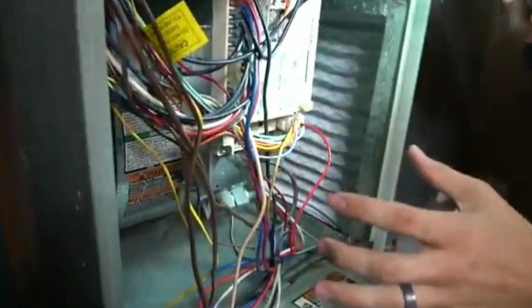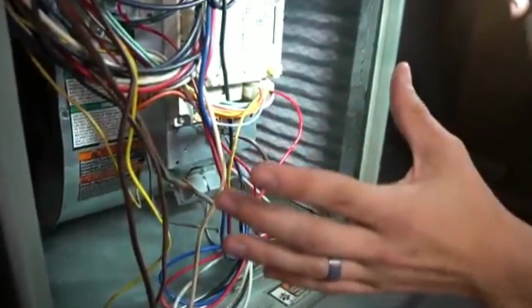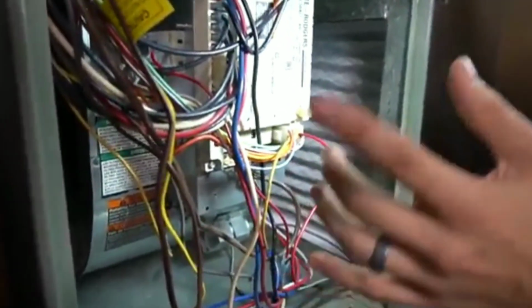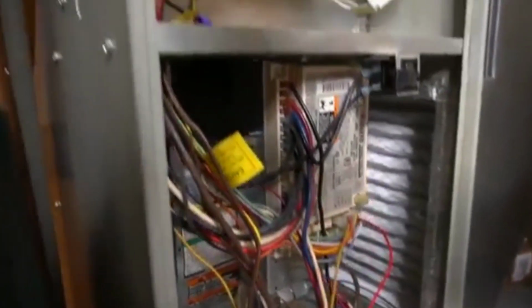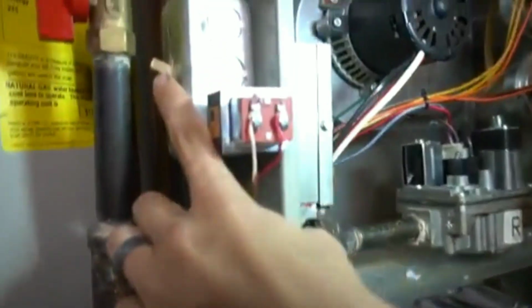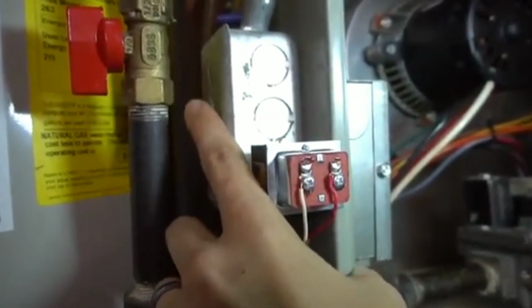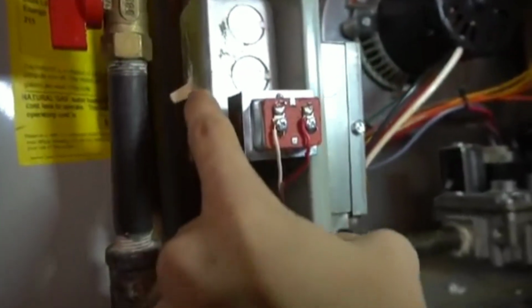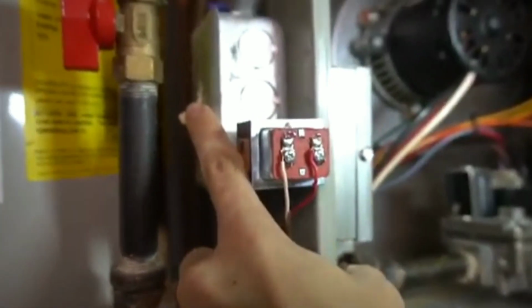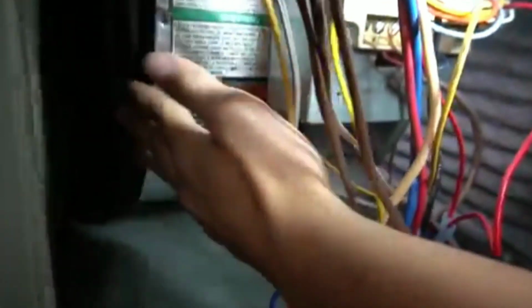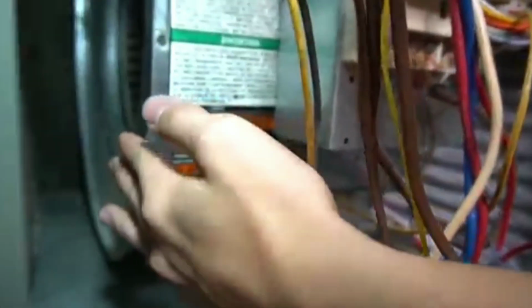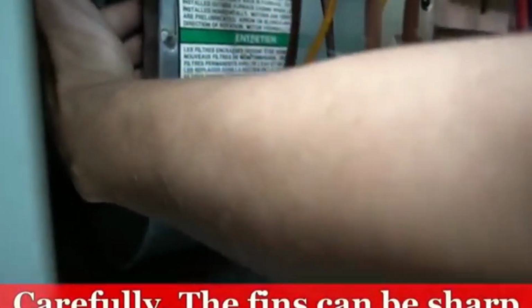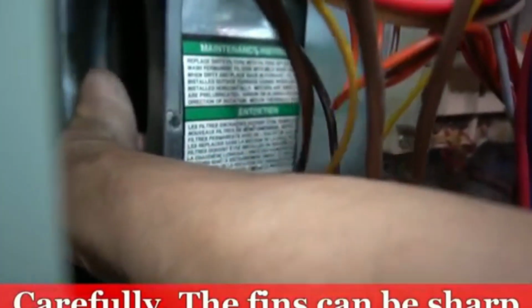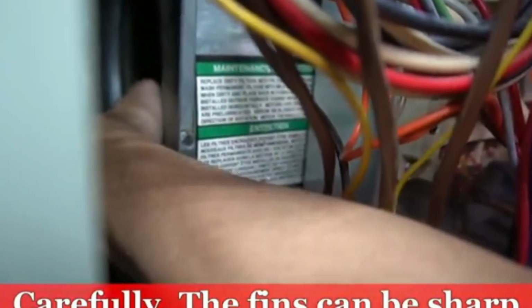After you take your bottom door off, make sure the power is off to your furnace. There's a power switch right here. On most furnaces it'll be on the side of the furnace. Or you can just go ahead and turn off your circuit breaker for the furnace. And then just reach in on one side of this blower motor housing, and just kind of feel with your fingers in between those fins.